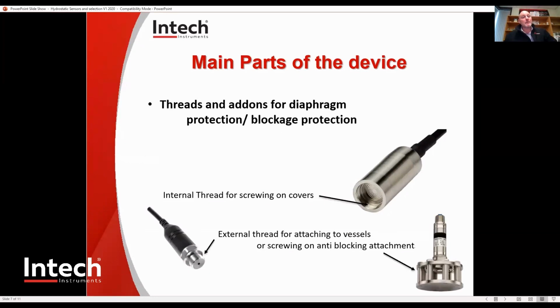Next is the threads and the add-ons for diaphragm protection or blockage protection. This is important for being able to attach it to something or for anything to be attached to it. Internal threads are good for covers, for being able to protect an open diaphragm. External threads are for screwing on to an underwater vessel or attaching a cage for thicker sewage applications, as you can see in the bottom of the image just there.